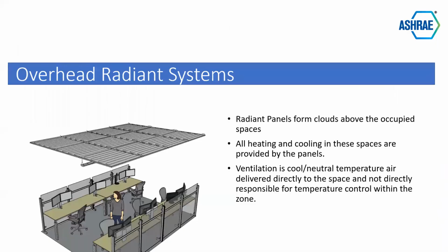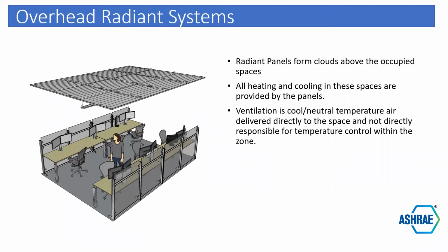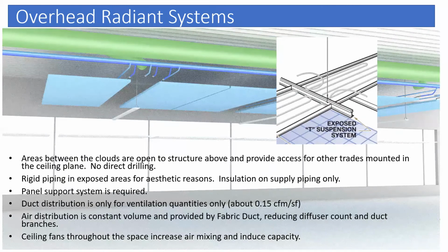So this gives you a sense of the radiant panel methodology and their overhead radiant systems. And they're actually radiant panel clouds, and they're open to the structure, provide access for other trades. Rigid piping in exposed areas, panel support system is required, and duct distribution is only for ventilation quantities, about 0.15 CFM per square foot.